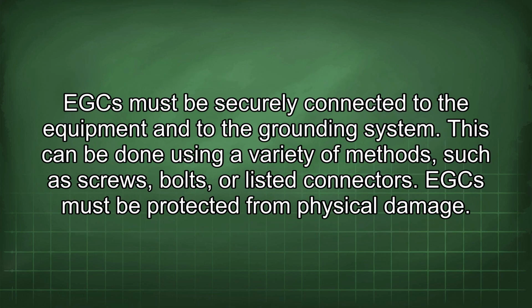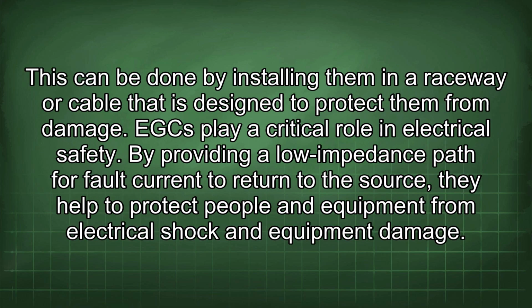EGCs must be securely connected to the equipment and to the grounding system. This can be done using a variety of methods such as screws, bolts, or listed connectors. EGCs must be protected from physical damage. This can be done by installing them in a raceway or cable that is designed to protect them from damage. EGCs play a critical role in electrical safety. By providing a low impedance path for fault current to return to the source, they help to protect people and equipment from electrical shock and equipment damage.